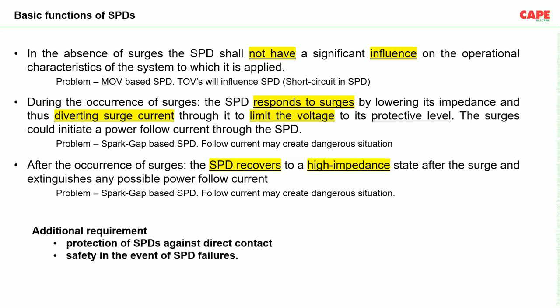Additional requirements have also been specified by the standard IEC 61643 part 12. First one is protection of SPDs against direct contact, that is very obvious. That means once an SPD is installed, we should not be able to directly touch the current carrying parts of the SPD. That protection we have to provide. Second one is safety in the event of SPD failure, which means once we have connected an SPD in a system, during the event where SPD comes to the end of its life, that means when SPD is about to fail, there are two possibilities.